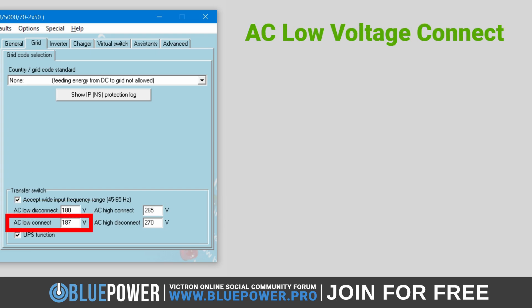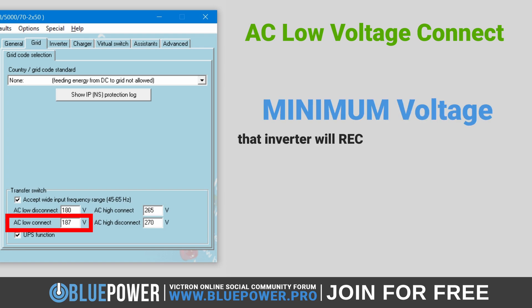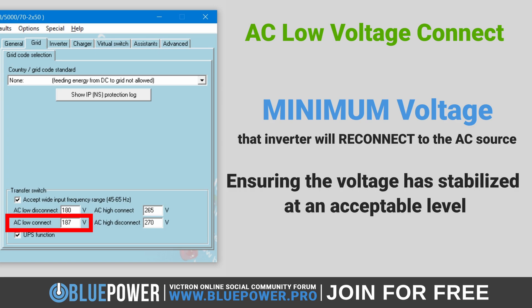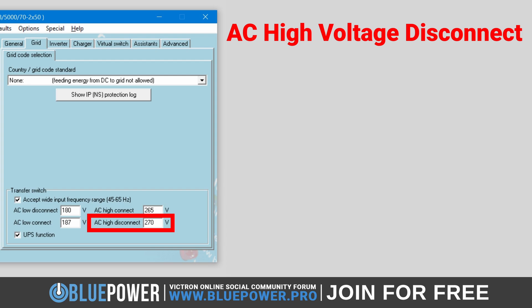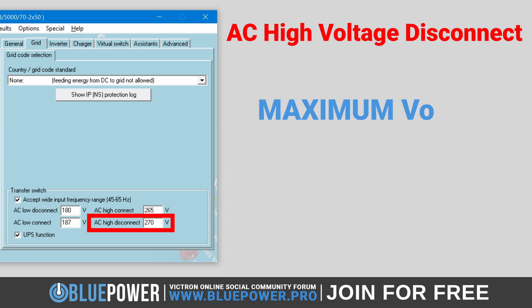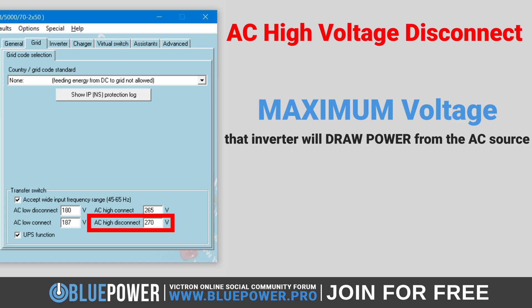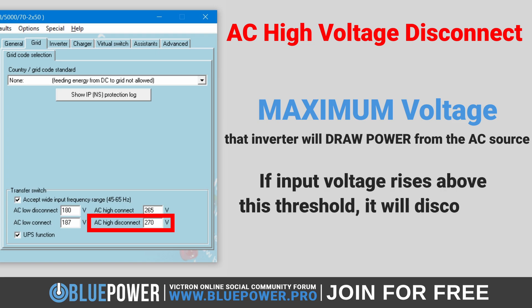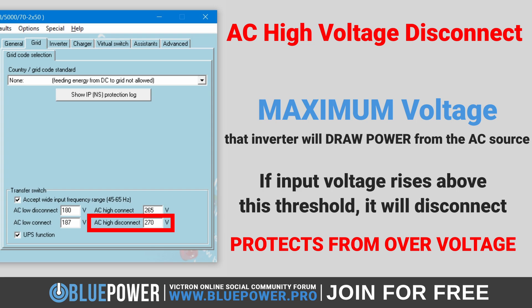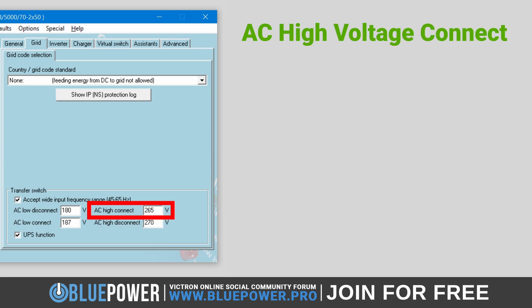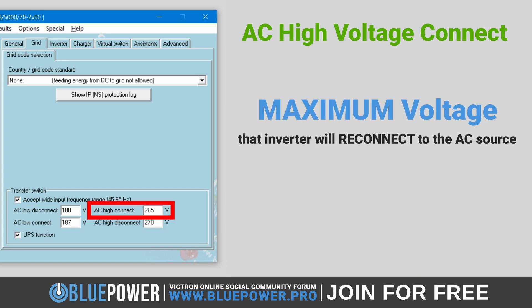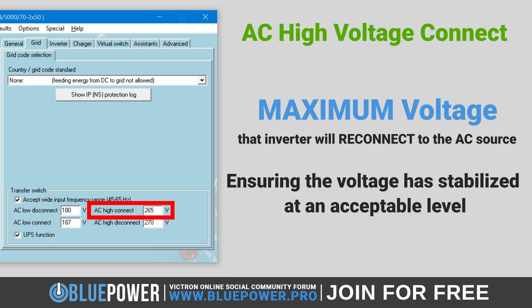Should a disconnection happen due to low voltage, the AC low voltage connect setting specifies the voltage at which the inverter will reconnect to the AC source, ensuring the voltage has stabilized at an acceptable level. In a similar manner, the AC high voltage disconnect setting will disconnect the incoming grid if the AC input voltage rises above this upper limit, thereby preventing over-voltage damage to the system and the appliances linked to it. Lastly, the AC high voltage connect setting is the voltage at which the inverter will connect to the AC source after being disconnected due to a high voltage disconnect, confirming the voltage has returned to a safe operating level.